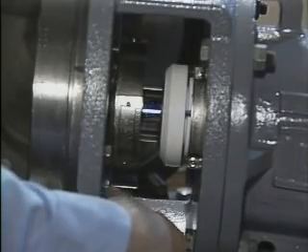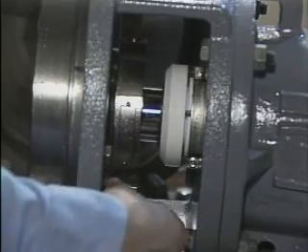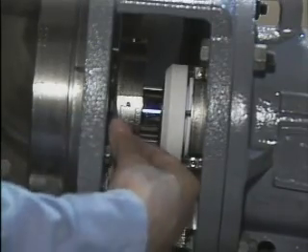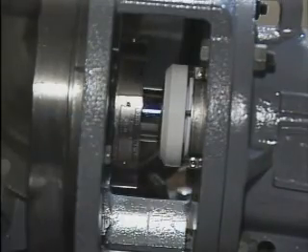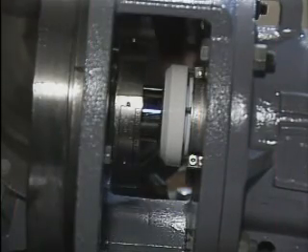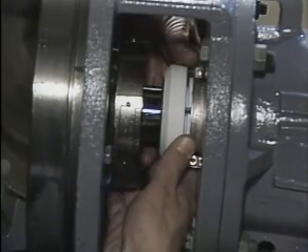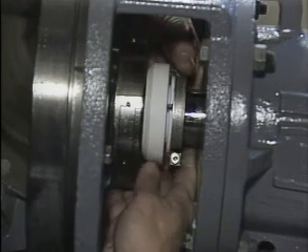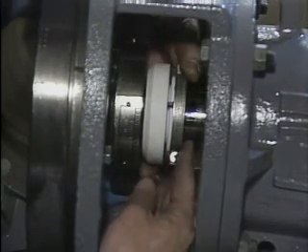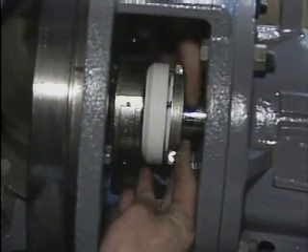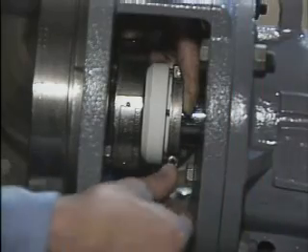The gap between the gland plate and the back plate is measured with a feeler gauge to make certain that the gland plate was tightened properly. Next, the rotating element is put into position so its collar is aligned with the scribe line that was made on the shaft when the location dimension was measured. Then the clamping screws are tightened.